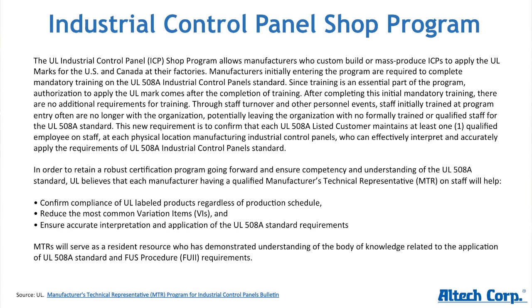For example, I read, to prepare for this little presentation here, some things where people take the UL listing mark of the panel enclosure, the metal enclosure essentially, as the UL approved listing mark for the UL 508A panel. You cannot make that mistake if you want to be sure you have all your ducks in a row with UL. So UL listed is not equal to UL listed.